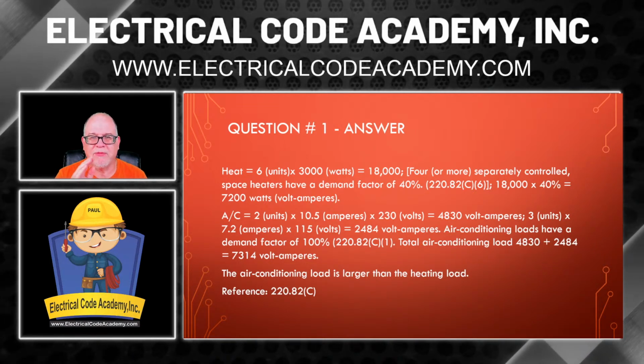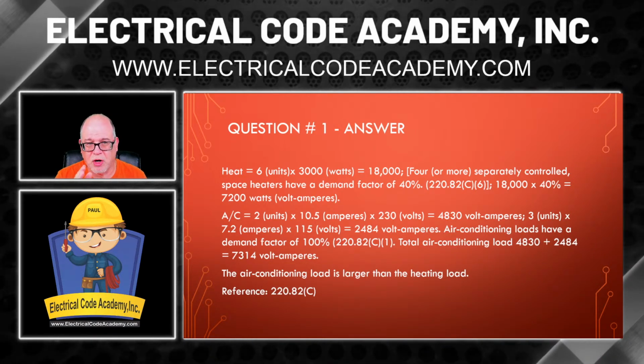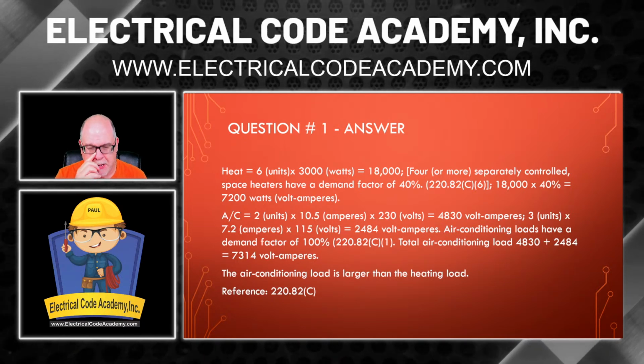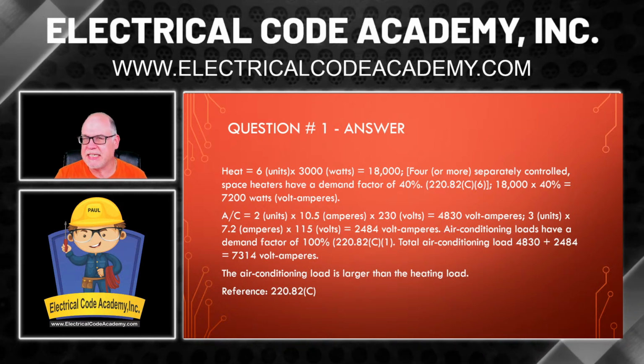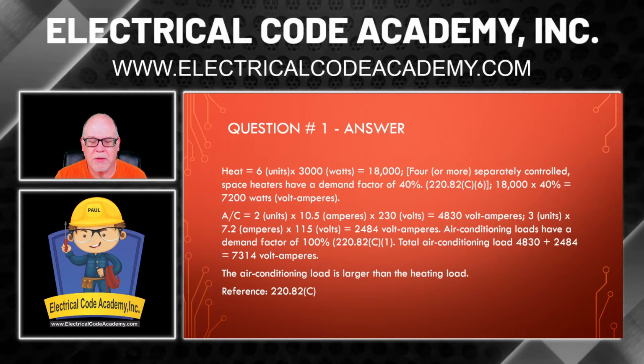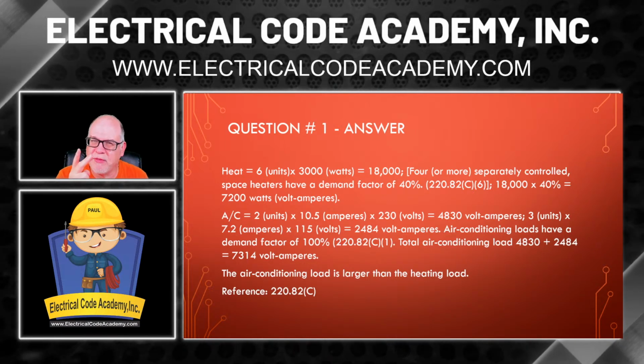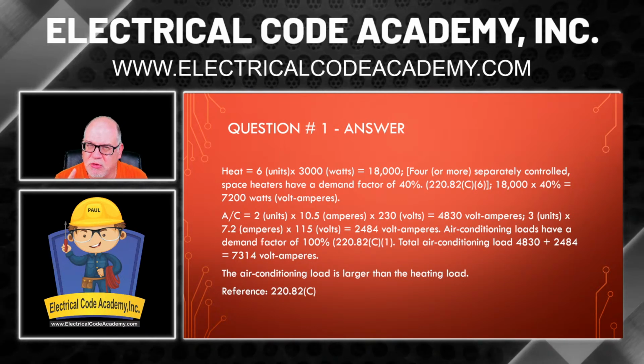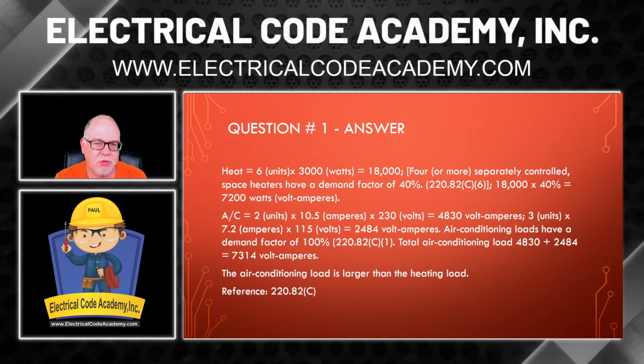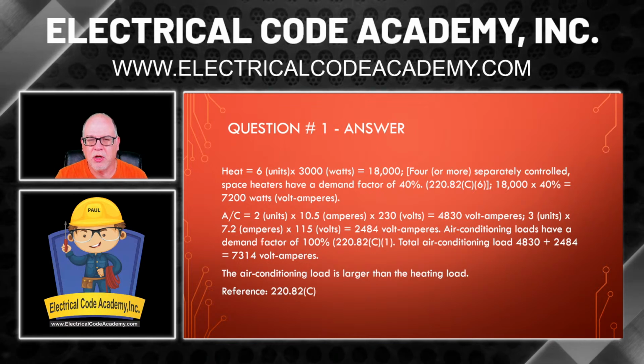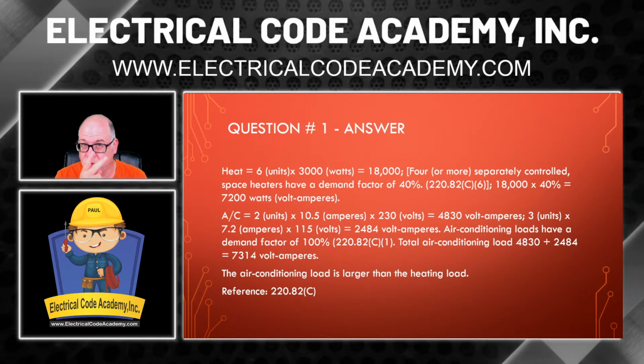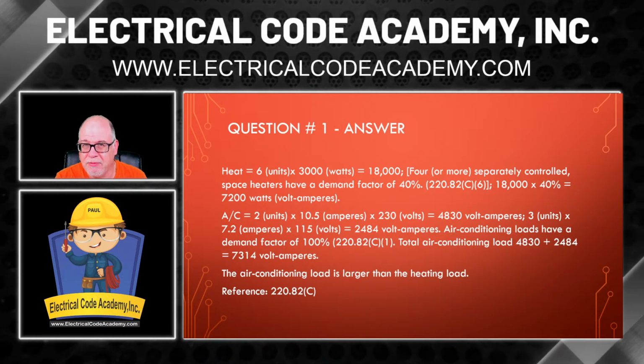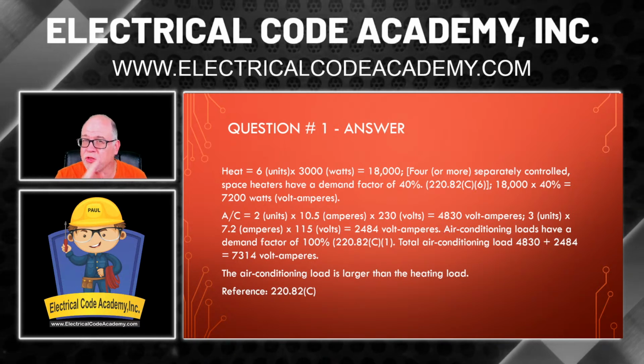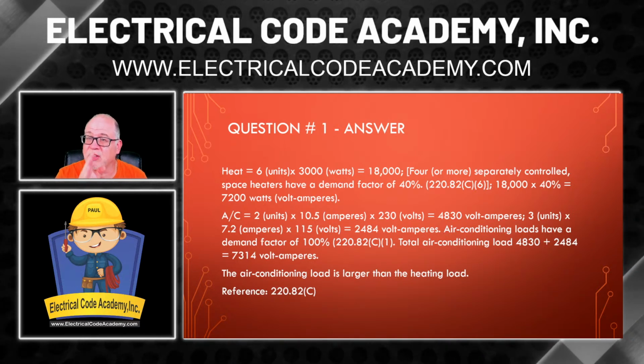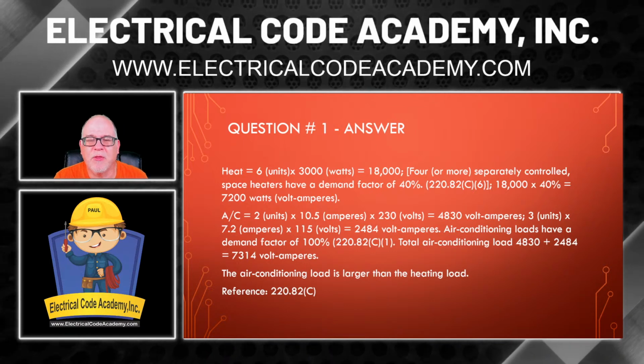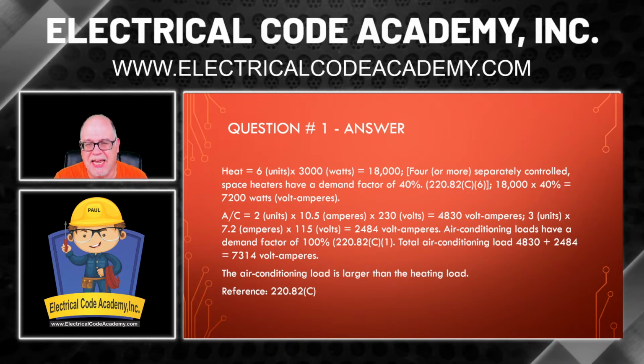Because we know that we've done the heat already, and 7,200 is what we're working with for the heat. Is that going to be greater than the AC? Well, that's what you have to work out. Remember, we had 2 of them at 10.5 amps each, and 3 of them at 7.2 amps. So, easy math: 2, because there are 2 of them, times 10.5 times 230 volts. Remember, use the voltage that's given in the question. That's going to give us 4,830 VA.